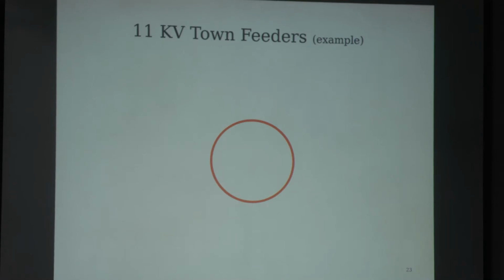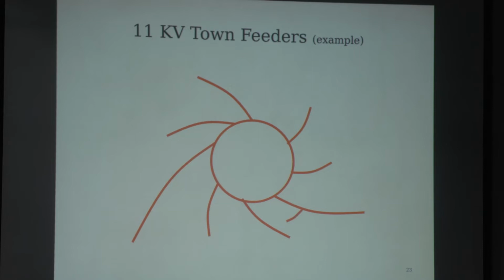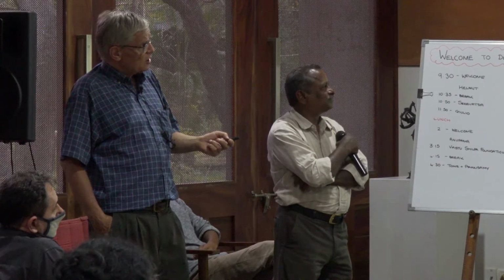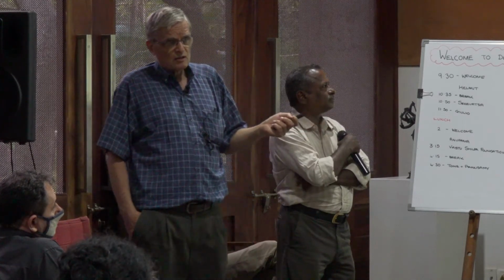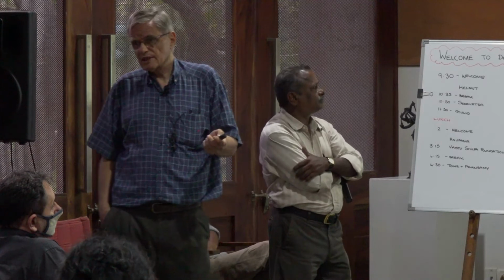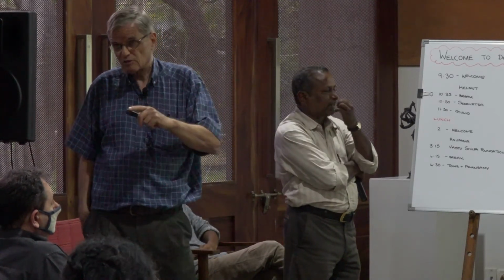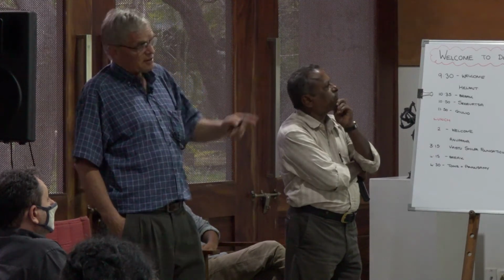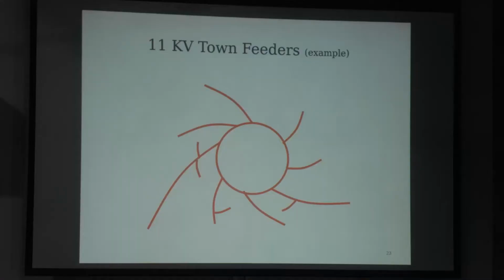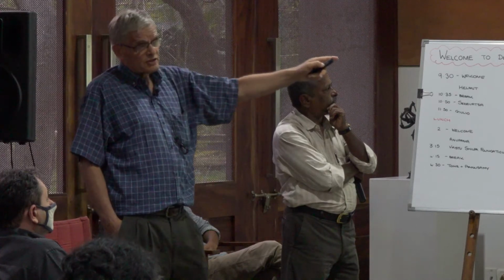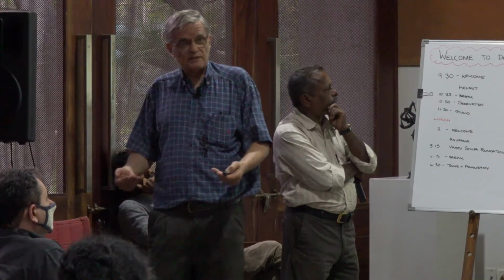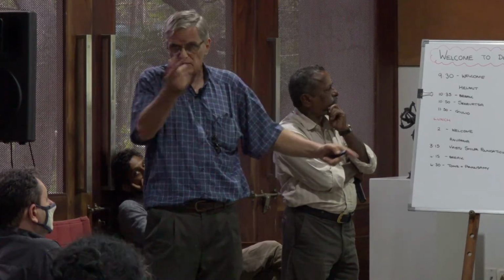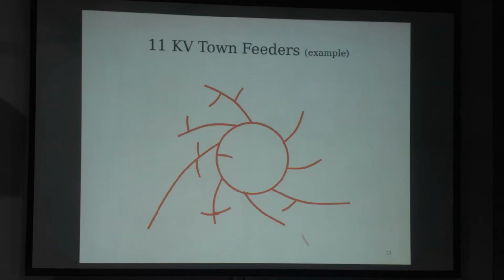So how would it work? You have a ring, and then along the radials you penetrate into the urban fabric — these are just illustrative, not literal. As the town grows, this is the nice thing, it's very modular. If the TDC decides to focus on Sector 1 and Sector 2 of the residential zone, designed for 5,000 people but where only 800 are staying, then that radial is built first, along with the spur lines going from it. You keep building on it, but the ring is like the foundation of a building — it has to be designed now for half capacity, and later the second cable is laid for the full capacity.